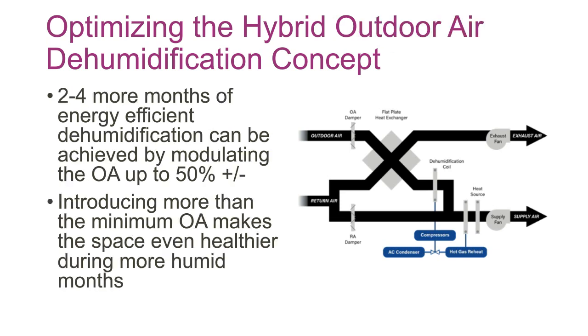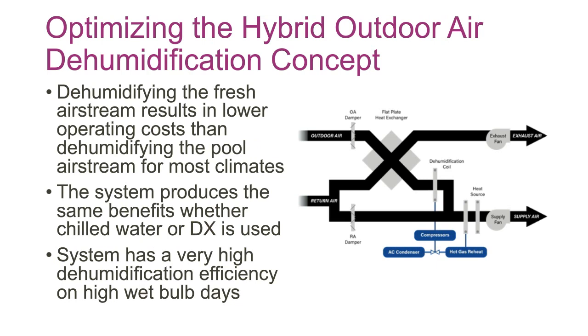Typically, compared to the ASHRAE minimum, using this concept, you can get 2 to 4 more months of energy efficient dehumidification by modulating that outside air up. Introducing more than the minimum makes the space healthier while you're doing that. So as a side benefit to the efficient dehumidification, you're also getting more fresh air to the space. Tends to result in lower operating costs than dehumidifying the pool airstream if you dehumidify the fresh airstream.